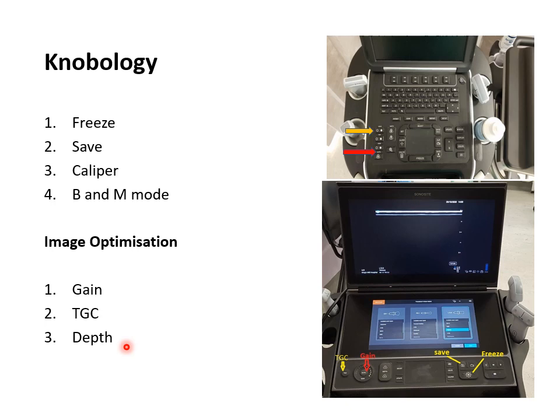For image optimization you can use three settings: gain, TGC, and depth. When sound waves travel from one structure to another and reflect back, they lose energy — the deeper the structure, the more energy is lost. Gain allows you to amplify the returning signals so that deeper structures can be compensated. TGC, or time gain compensation, is similar to gain but allows you to selectively amplify the returning signal at certain depths. So gain amplifies all signals, while TGC lets you choose whether to amplify signals from superficial, middle, or deeper structures.